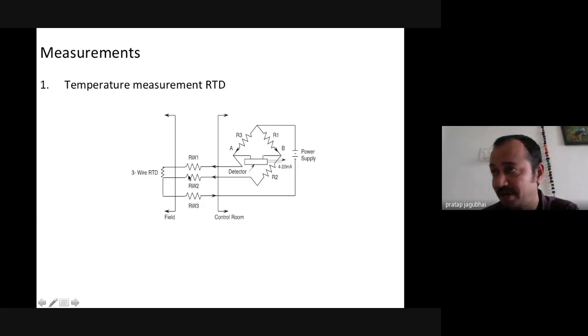Further, you can have a compensation available because the long lead to the temperature element is very far, and you have taken the wire, so you can have a compensation such that the effect of this additional resistance will be eliminated. So it is taken as a 3-wire and can be taken as a 4-wire also.